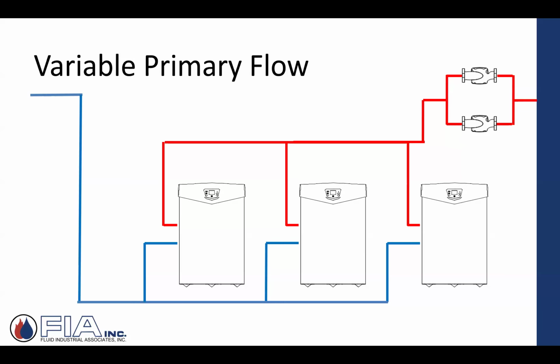Now, there's all different little details. We might get into control valves for the boilers that aren't firing. We don't want system flow going through an off boiler, perhaps, and we can talk about that. But this is a common application, and sometimes the argument or the conversation would be, I'm using fewer pumps. I don't have smaller boiler pumps or secondary pumps for my boilers, and I don't have distribution pumps.